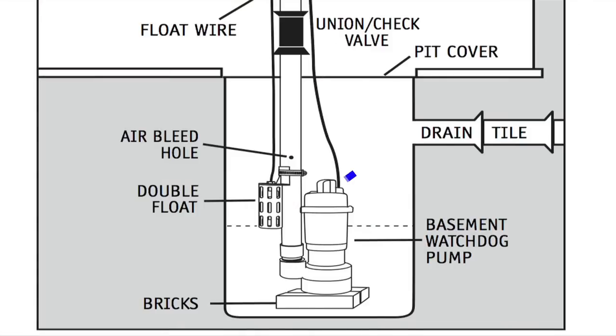Position the float switch so the bottom of the float is below the drain tile and the float is facing away from the drain tile so the water will not splash on it when it fills the sump pit.